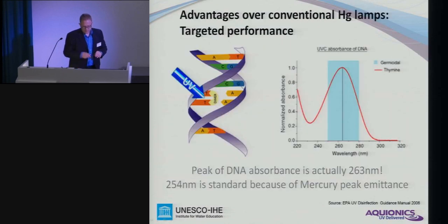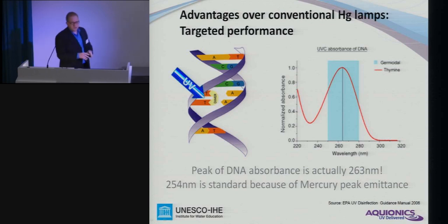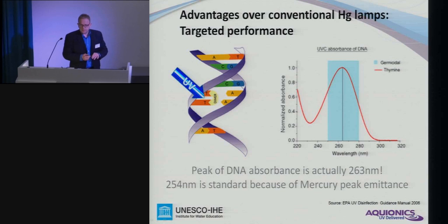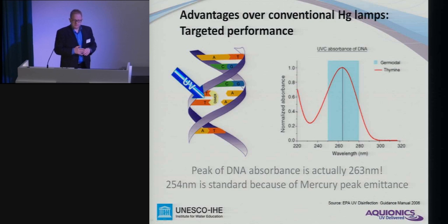In terms of the wavelength, we hear a lot about 254 nanometers, which is basically the peak emittance of mercury-based lamps. But as a matter of fact, the peak absorbance of the DNA — so the most effective wavelength for disinfection — is at 263 nanometers. That's not so easy to produce, so everything seems to be standardized on 254 by now. That's well established and we can't ignore this, but reality is that 263 would be better and more efficient.